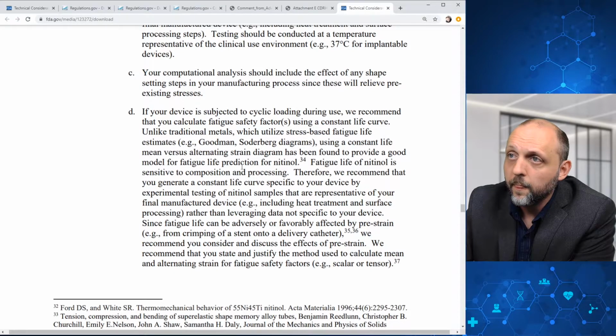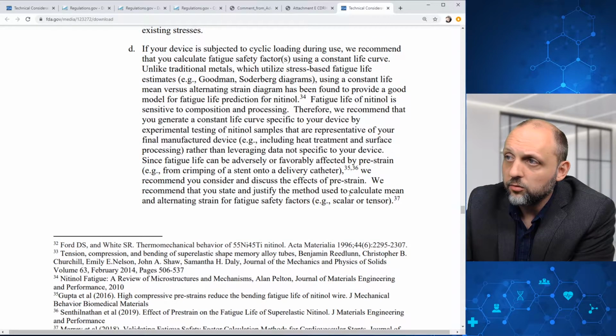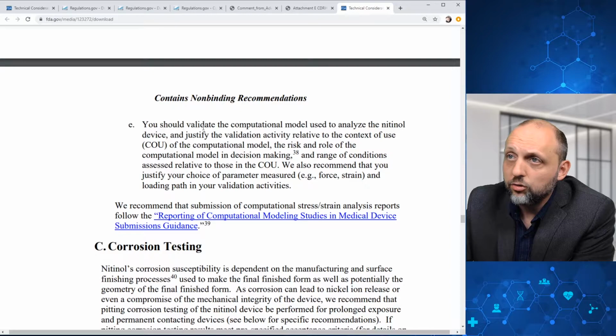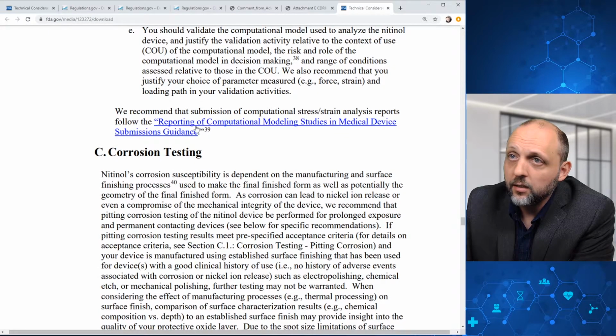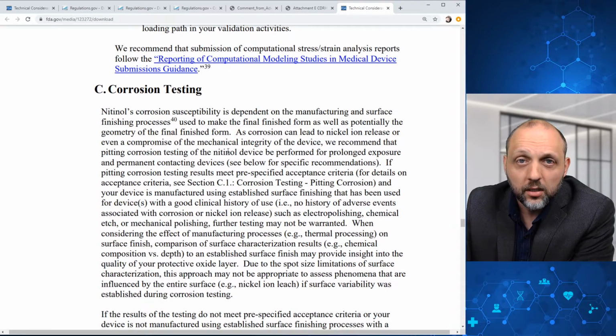constant life curve, and recommends that you state and justify the method used to calculate mean and alternating strain for fatigue safety factors. And you should validate the computational model used to analyze the nitinol device and justify the validation activity relative to the context of use of the computational model, the risk and role of the computational model in decision making, and the range of conditions assessed relative to those in the context of use. FDA also recommends that you justify your choice of parameter measured and loading path in your validation activities. And then FDA references this specific Computational Modeling Studies in Medical Device Submissions guidance.